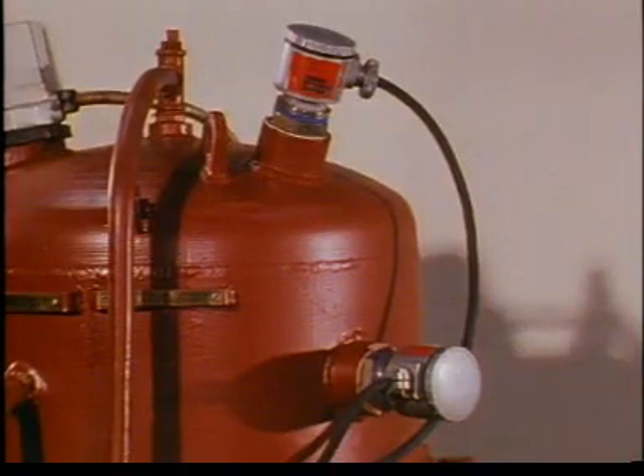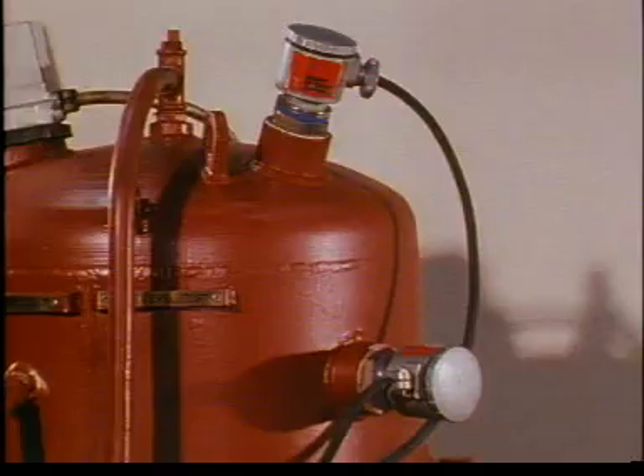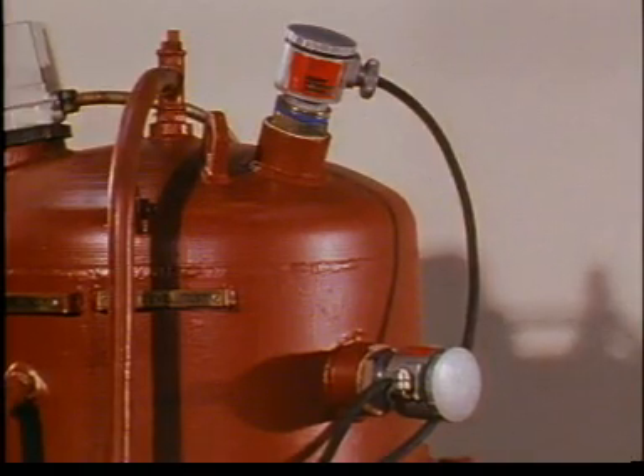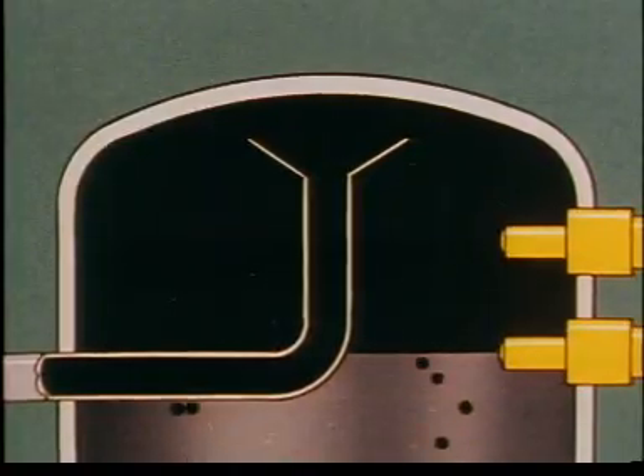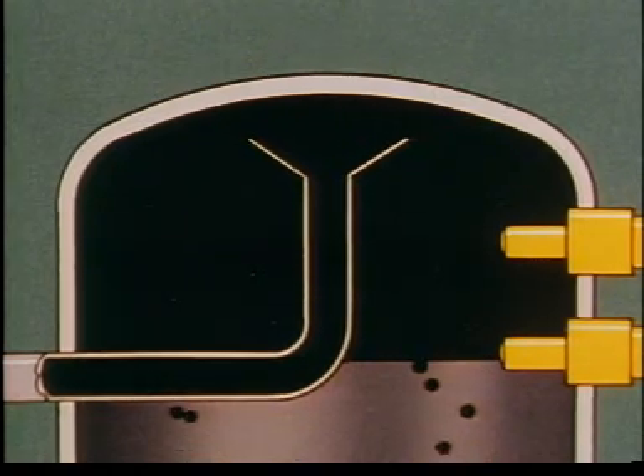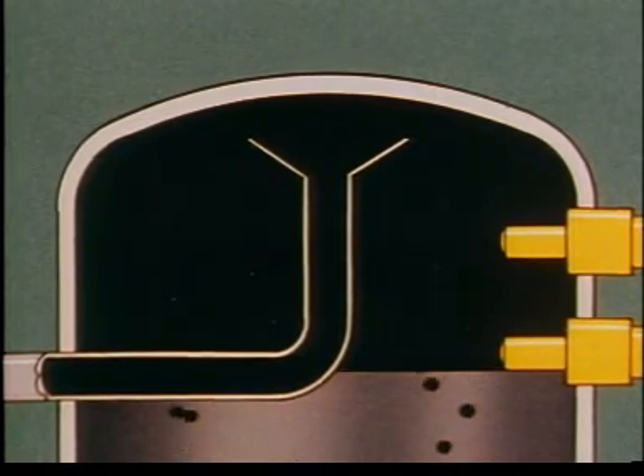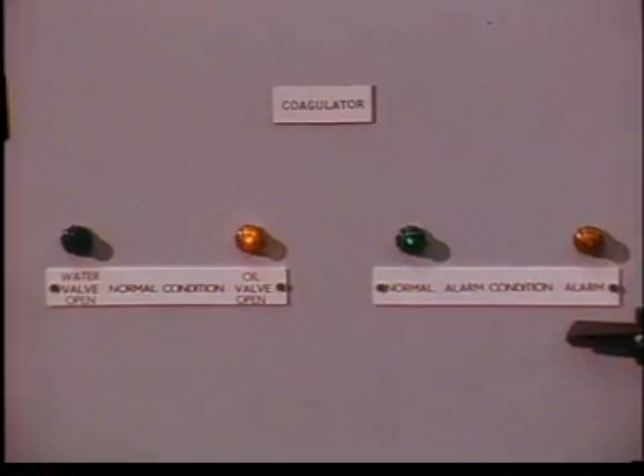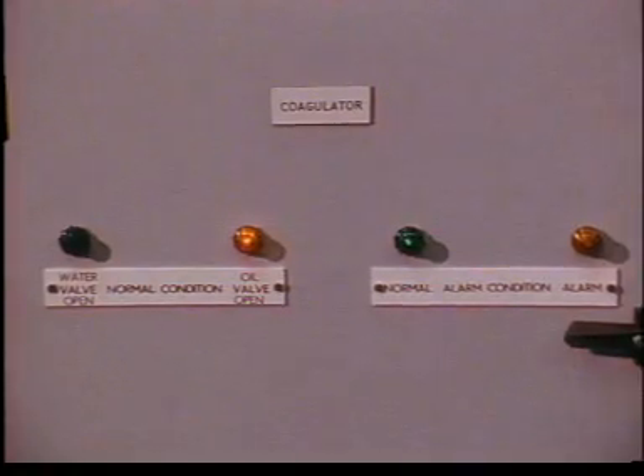The lower probe is a safety device in case the upper probe fails, or in case the oil outlet valve remains closed. In such circumstances, the oil-water interface will continue to descend until oil covers the lower probe. When this happens, the light for the low level on the control panel will change from water to oil and can be arranged to trip the pump motor or sound an audible alarm.